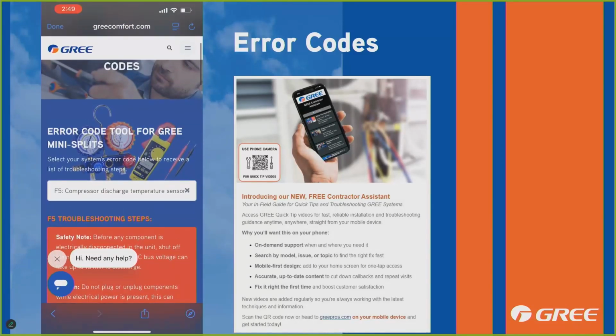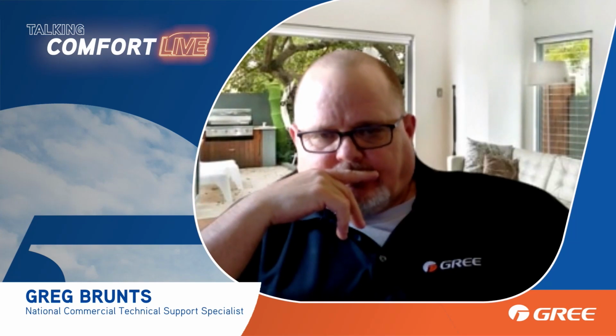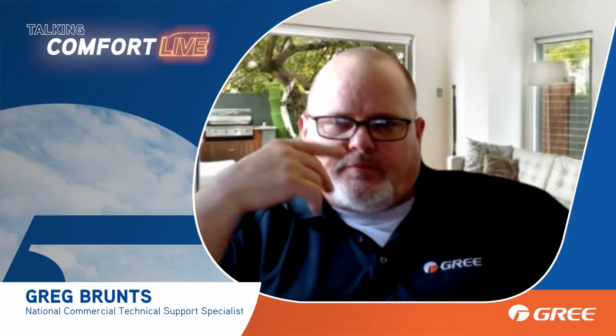Just a personal note here: well over 9 times out of 10, if you've got a sensor error code, it's going to be that the sensor is open or short. But we give you the method for testing that, to ohm out the sensor and ensure it's open or short. If it is, what do you do? You replace it. That's it.